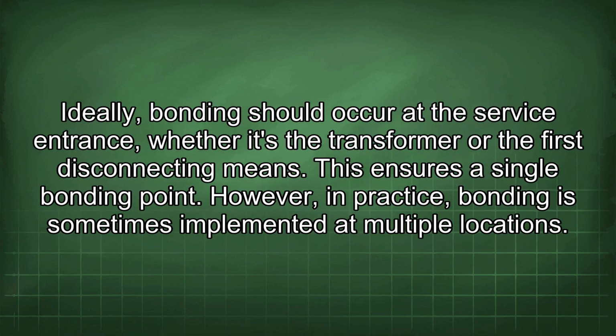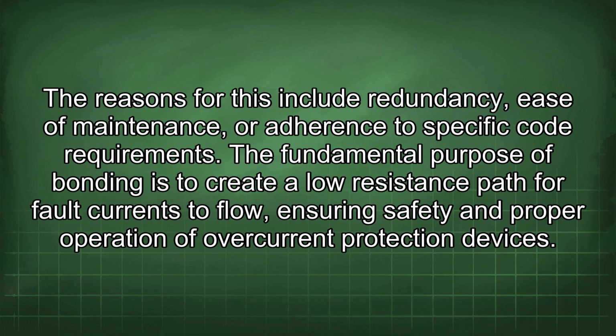Ideally, bonding should occur at the service entrance, whether it's the transformer or the first disconnecting means. This ensures a single bonding point. However, in practice, bonding is sometimes implemented at multiple locations. The reasons for this include redundancy, ease of maintenance, or adherence to specific code requirements.